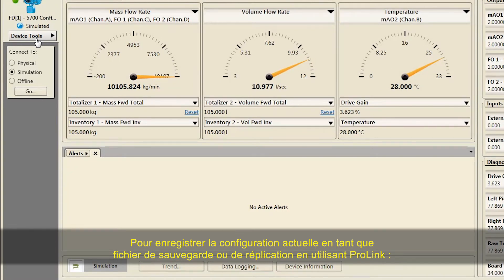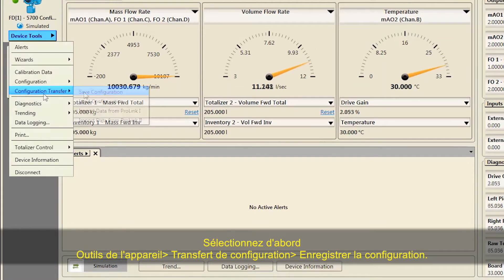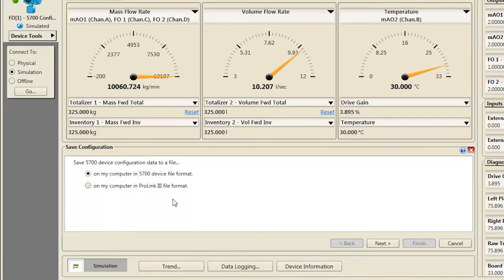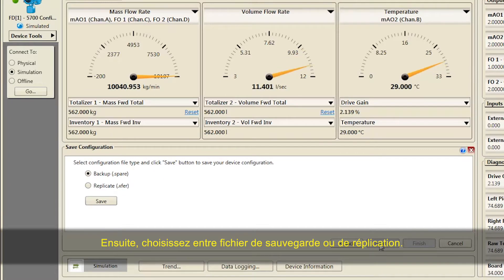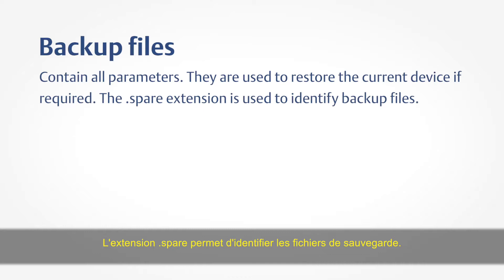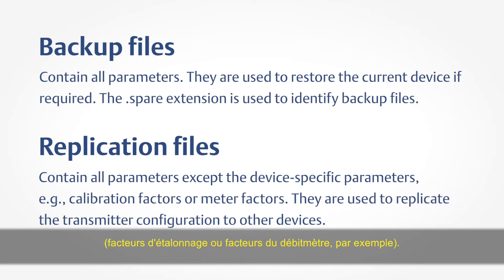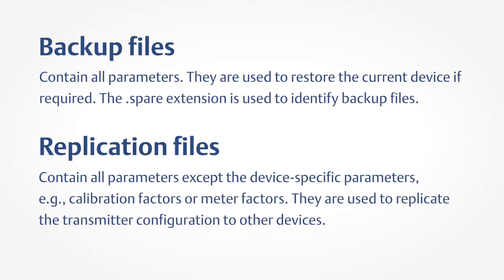To save the current configuration as either a backup file or a replication file using ProLink: first, select Device Tools > Configuration Transfer > Save Configuration. Second, choose Backup or Replicate File. Backup files contain all parameters and are used to restore the current device if required — the .spare extension identifies backup files. Replication files contain all parameters except device-specific parameters such as calibration factors or meter factors, and are used to replicate the transmitter configuration to other devices.